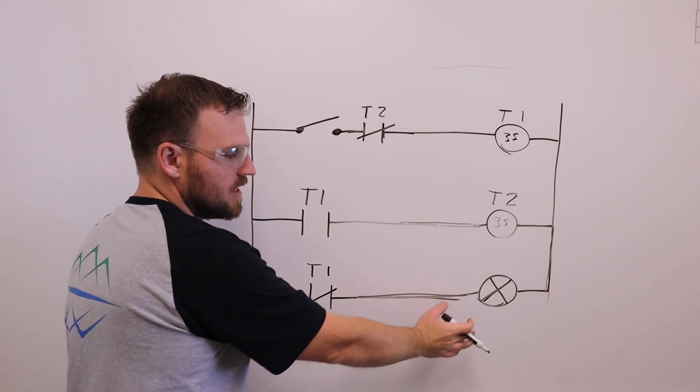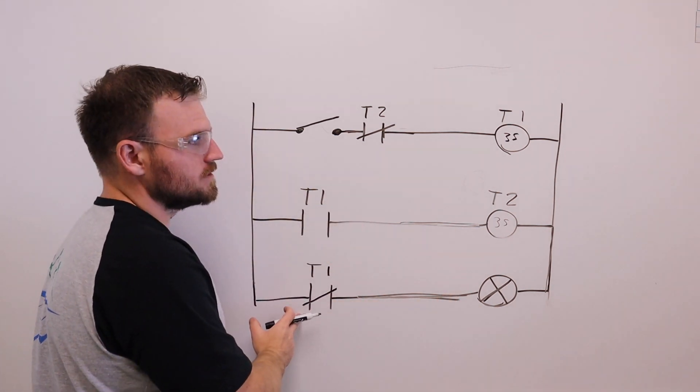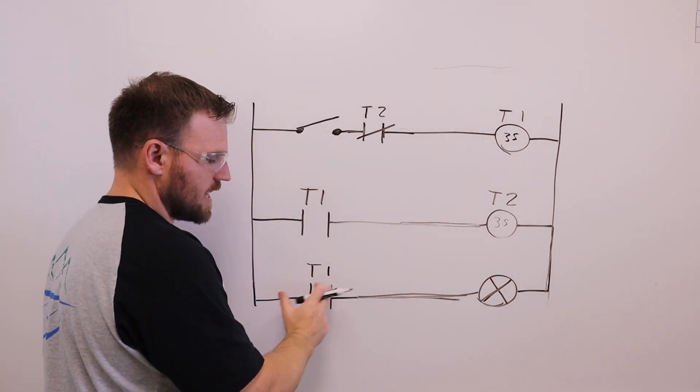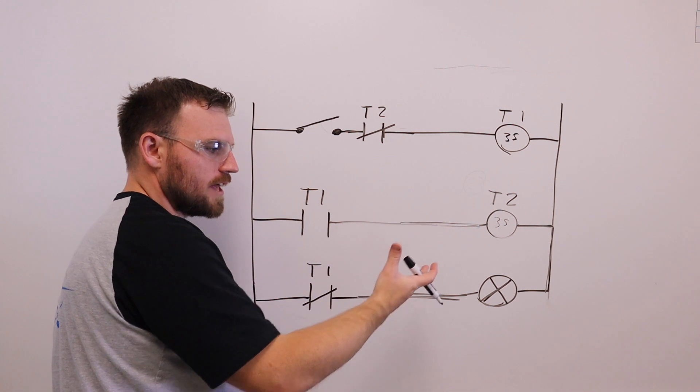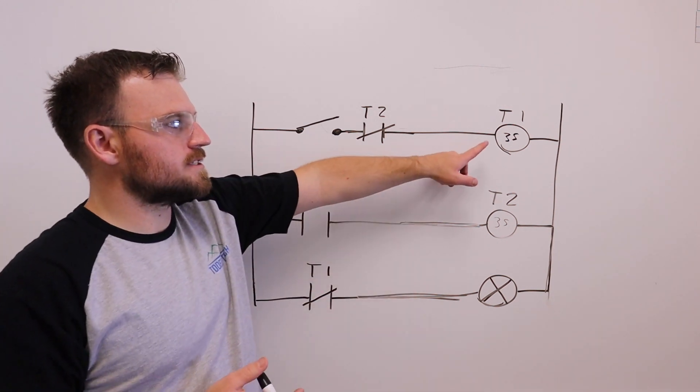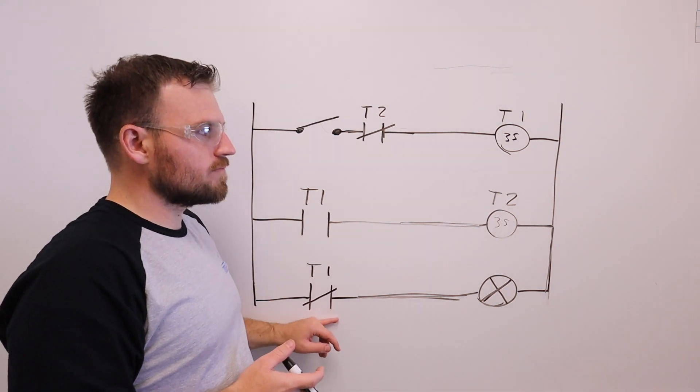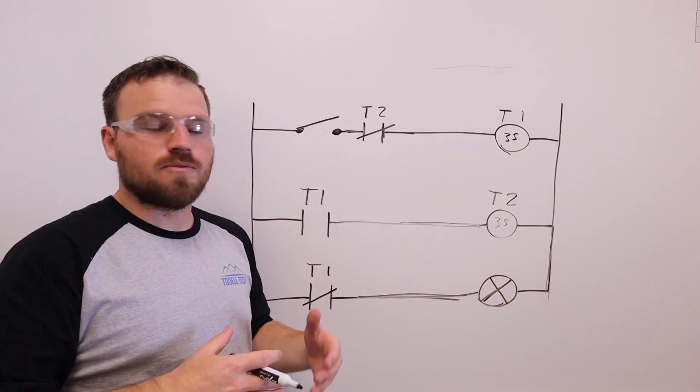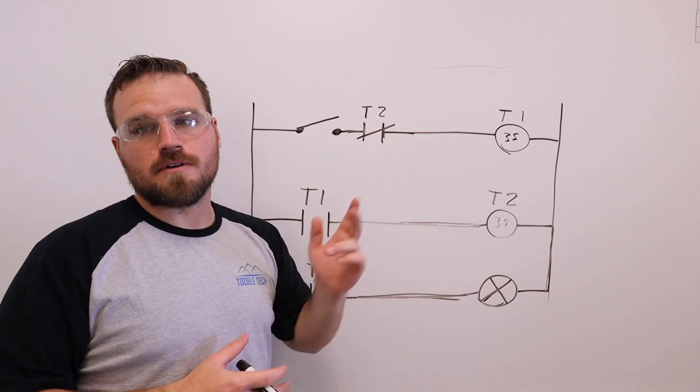Now, I've connected the light to T1. So every time T1 comes on, it's going to open this contact, turning off the light. So the light will normally be on. So what I've really got set up is three seconds it's going to be on, and then three seconds it's going to be off. We're giving a timer for on and a timer for off.